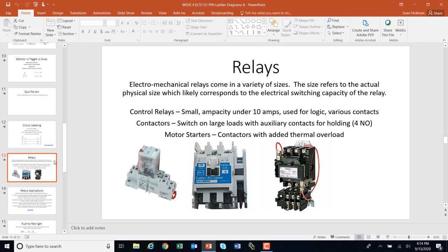A control relay is small — its ampacity might be 10 amps or 5 amps, typically under 10 amps. It's used for logic purposes like holding circuits. It has various types of contacts, and you'll need to recognize it and know how to hook it up. A contactor is bigger in size and primarily larger in ampacity. It'll typically have four contacts — often four normally open contacts — with contacts one, two, and three for lines one, two, and three of the power circuit, and another contact for holding. Contactors are good for switching large loads: 10, 20, 30, 40, 100, even 200 amps.